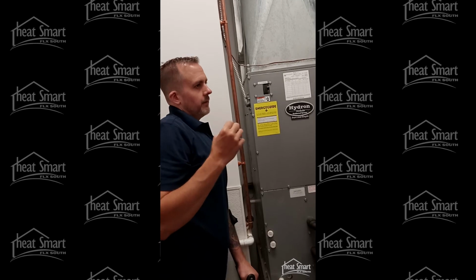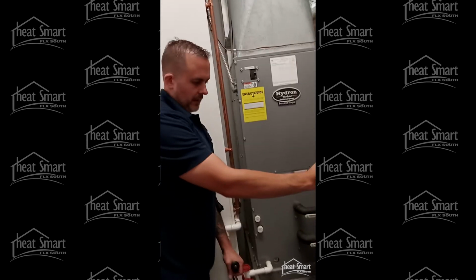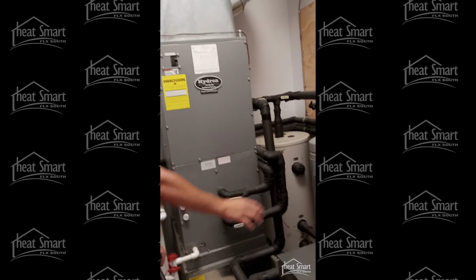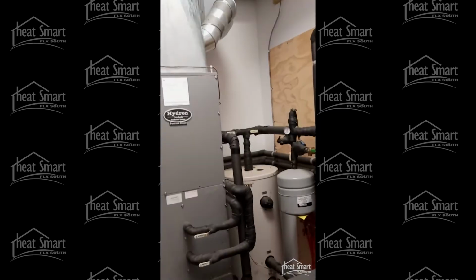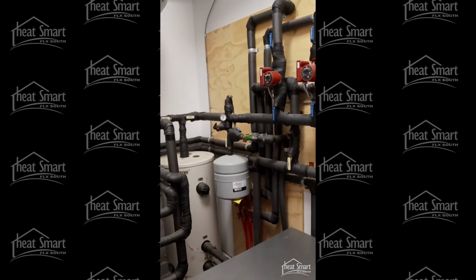And if there's any humidity, it's going to condense, just like a glass of iced tea or something. Same thing's going to happen if you have cold water running through a warm space. It's going to condense. So that's why it has to be heavily insulated, to keep condensation from making a mess.